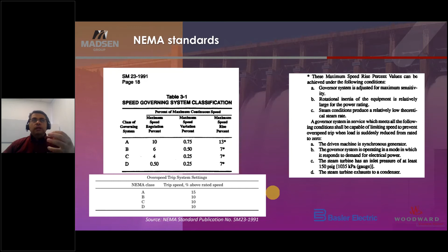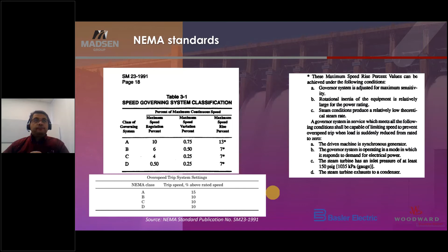Again, when we talk about the overspeed, how much trip overspeed is allowed for NEMA A is up to 15%. For NEMA D kinds of governors, it's allowed up to 10%. So these are the standards that, when we design a controller, we need to make sure that we achieve these values. Otherwise, the controller will not meet the standards of NEMA or meet IESO, which is the Ontario power generation standards.